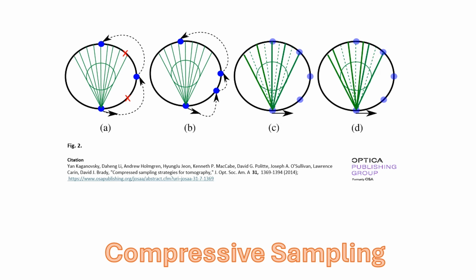So we have shown that if we have the complete set of rays going through an object, we can reconstruct the object using the projection slice theorem. Here we have a vertex of points. This is common with X-rays, that the X-ray is going to come from a single point. Rather than measuring a parallel set of rays going through the object, we measure a fan of rays that come from a certain vertex point, and then we can move the vertex point around the object to try to sample all the rays through the system.